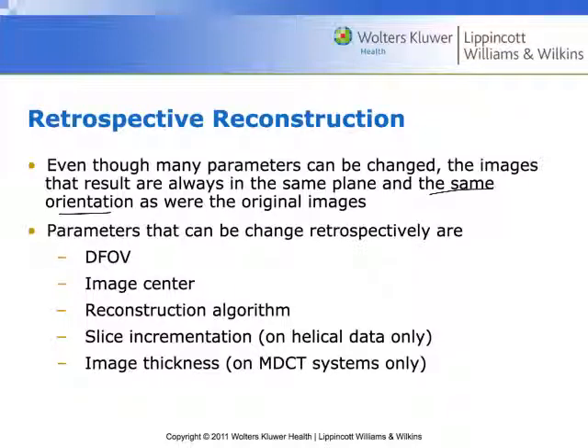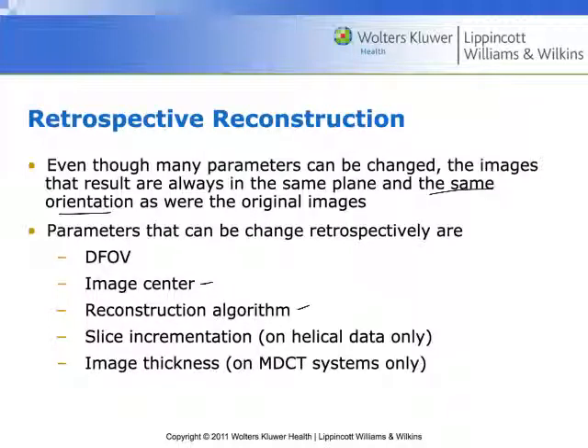The things that we can change include the display field of view — say the scan was scanned at too small of a display field of view, we can increase that. We can also change the isocenter or the image center. We can change the reconstruction algorithm — for example, we could add a filter to filter out metal, or we could use iterative reconstruction techniques in retrospective reconstruction.